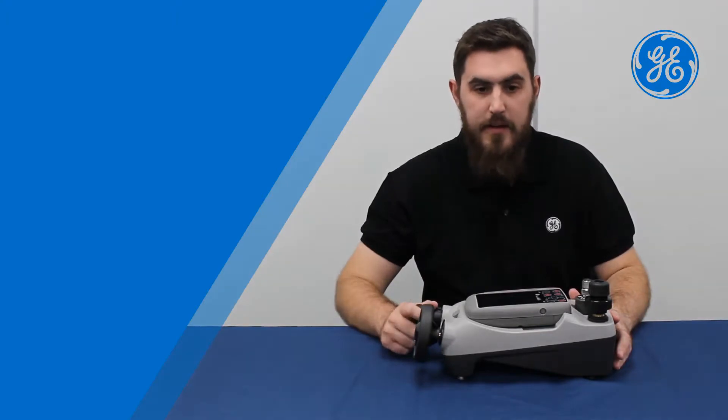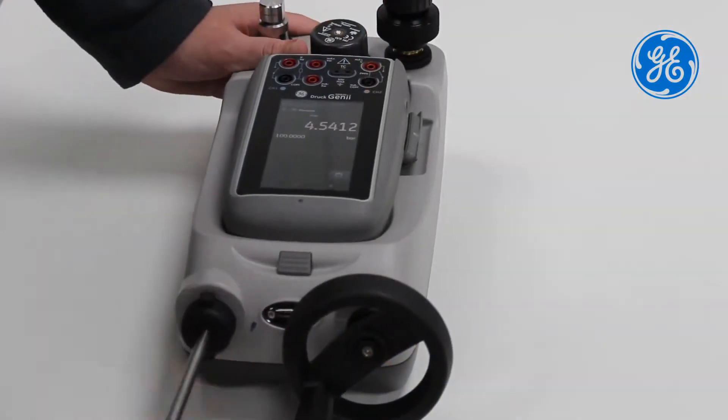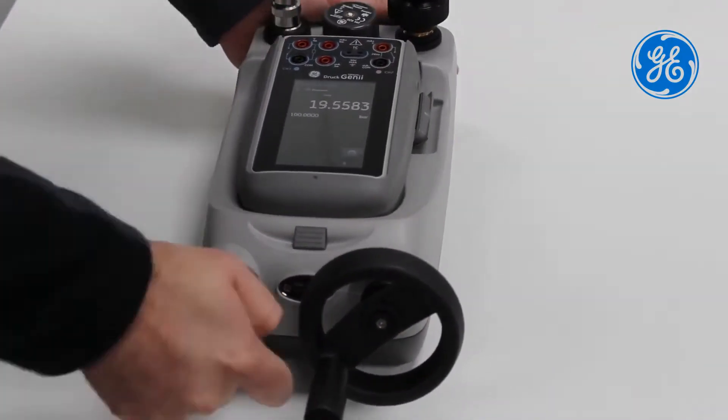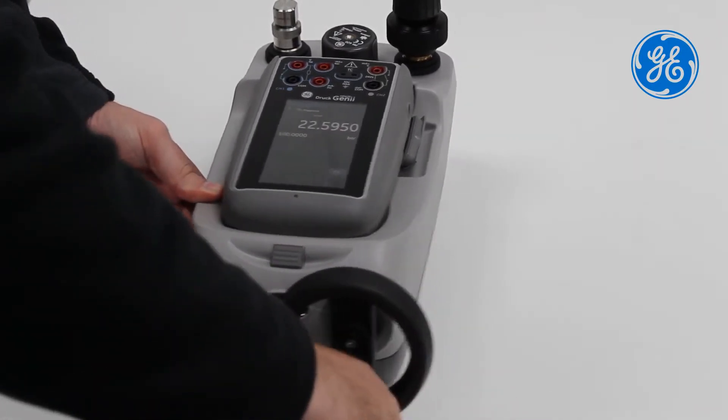Then I go ahead and start generating my pressure. I want to get up to 20-ish bar with the pump before going to the volume adjuster. And then using the volume adjuster, I go all the way clockwise up to 100 bar.